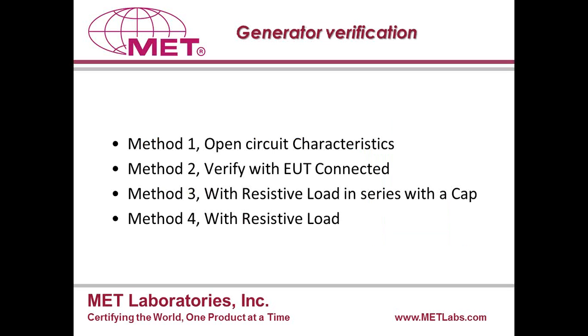That's exactly what happens. So a large number of generators in the industry would not or cannot possibly be verified using this method. And the standard clearly states all these methods are not equal, meaning if you validate your generator with a resistive load, that does not mean that your generator should also automatically be validated by method 1 or 2 or 3. These methods are not equal. So if you are validating your generator with method 4, that does not necessarily mean that it also complies with the other validation methods or vice versa.